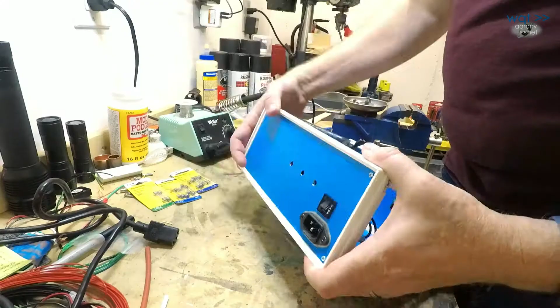You always go through your protective fuse or circuit breaker before going through your power switch. So straight off of this filtered IEC inlet, there's a jumper to this, and then this comes back out via the black wire over to the front panel switch. Output of the front panel switch is this blue wire, which comes around underneath here and ties into the transformer. Once we go through the primary of the transformer into black, brown is tied off on the primary because as a tap we're not using. White goes to neutral, back to the outlet.